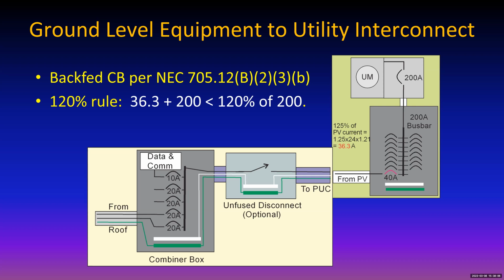the rating of the main circuit breaker, that 200 amp breaker up there, has to be less than 120% of the bus bar rating. Well, 36.3 plus 200 is 236.3, 120% of 200 is 240. So we're good. So we can do this, provided there's room for that breaker at the bottom of the panel. If there's room for one in the middle of the panel, maybe you can shift a few up and make this one available at the bottom. So this is one way to do it, okay? And it's very common. It was extremely common long ago, and now some more elegant, sophisticated ways of hooking in have been developed, and we're going to take a look at them as well.